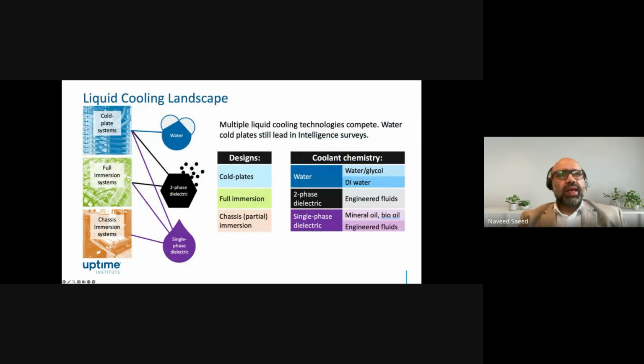So the liquid cooling landscape looks like three major categories of fluid being used: water, two-phase dielectric fluid, and single-phase dielectric fluid. Water and deionized water, and single-phase and two-phase, are all used in cold plates. Water and deionized water are not used for full immersion cooling. For full immersion cooling, it's either single-phase or two-phase dielectric fluids, and for chassis or partial immersion, it's also either two-phase or single-phase dielectric.